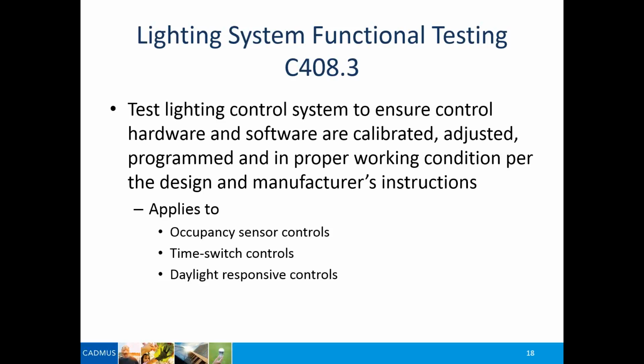And the one big thing about lighting controls is you're not going to get the energy savings unless the controls are set up properly. And this is the key thing. So the new requirements in the 2015 code actually require you to do functional testing to make sure that the lighting controls are set up properly. If you have daylight responsive lighting controls, to make sure they're actually put in the daylight zone, so they operate the way they're supposed to, and they're set up to be able to dim the lights the way they're supposed to and as designed.